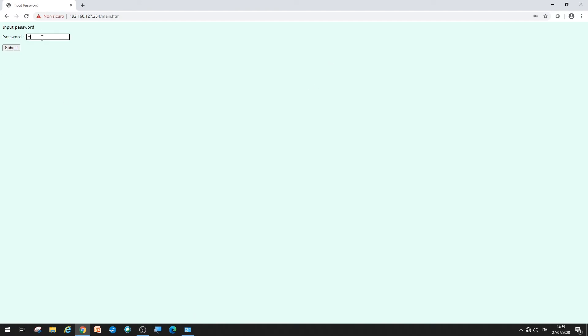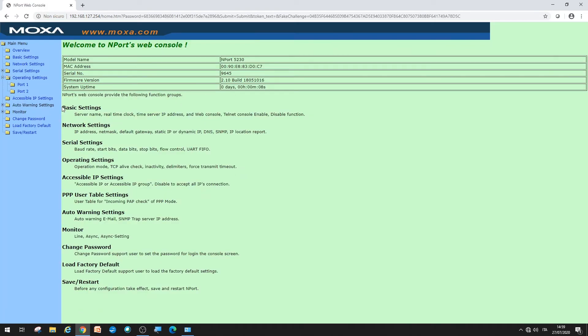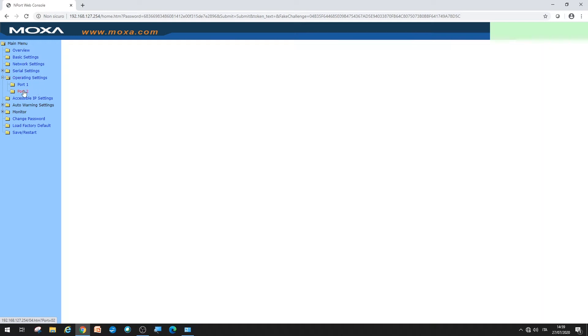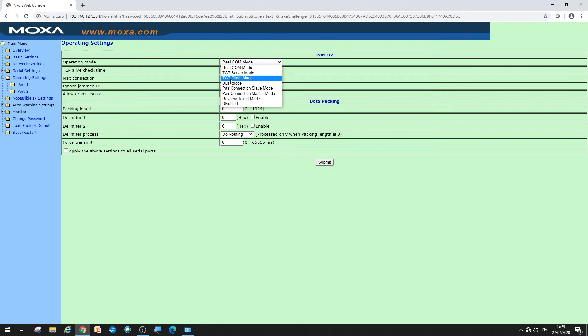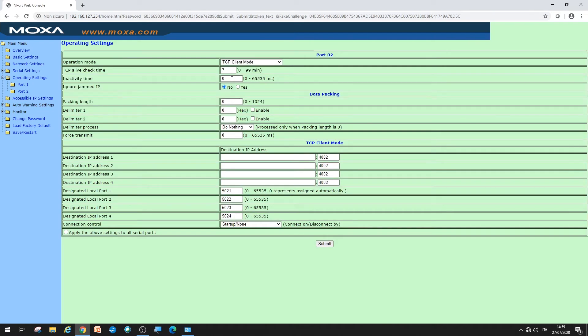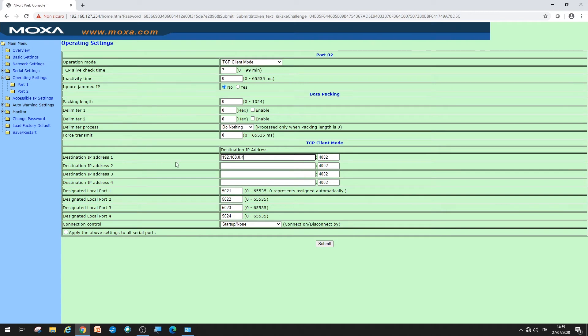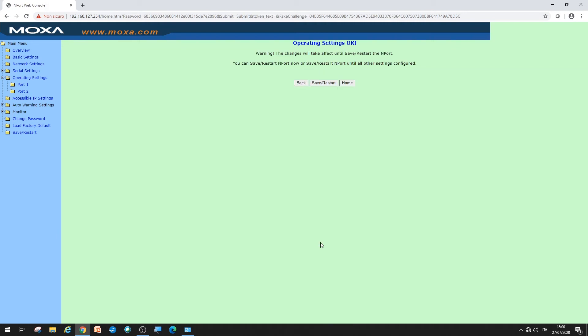Now it's time to enter the operating settings menu, again for port two. Set the operation mode to TCP client mode. You must specify the IP address of the gateway data logger EXC GA-01 in the fields that are shown. In this case, it is 192.168.0.4. The value of the TCP port must be 1000. Confirm with submit and then save and restart.